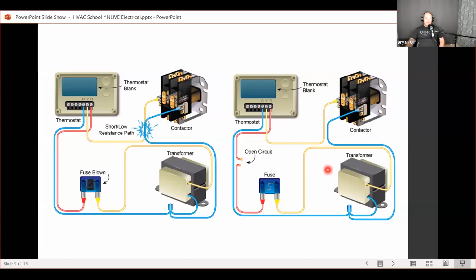A good example would be that this is a short circuit, but once it blows the fuse, now this is an open. So the short circuit causes an open. And the same thing is true of a circuit breaker, right? When you have a shorted compressor, the short causes the breaker to open in order to protect the wires.